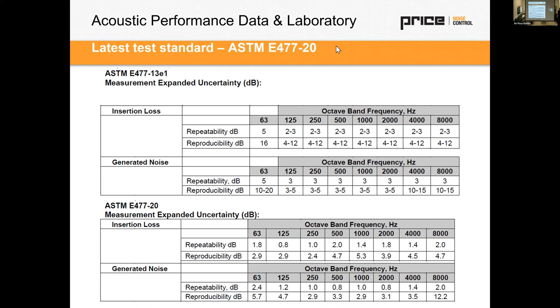Well, sort of like, what's the point if you're off by it? I mean, 3 is not terrible, but 5. Well, so reproducibility means I take the Price silencer and I go over to Armstrong and I stick it in their lab. And we have 16 decibel difference. Correct. In insertion loss from one to the other. Correct. That's a pretty big deal. That's a big difference. But just taking it out of your lab and then putting it back in a couple of days later and you get a 5, that's pretty big. Correct. Yeah, and now, you know, that 5 is now 1, maybe 2 if you round up.